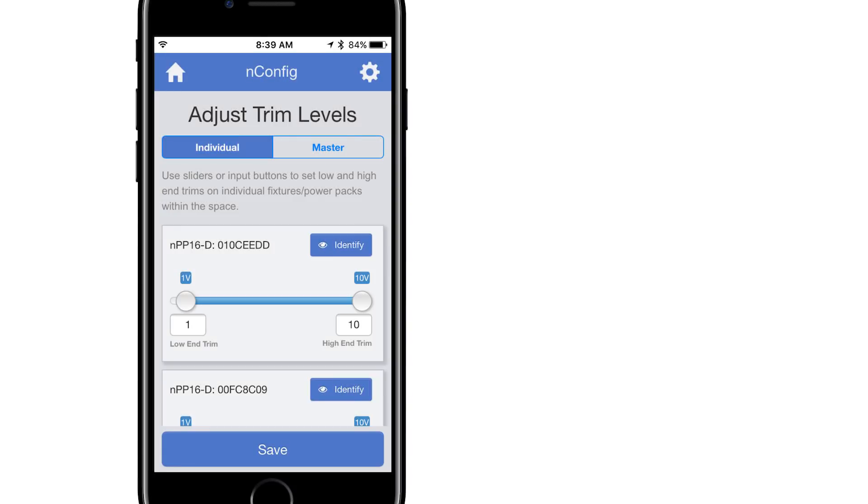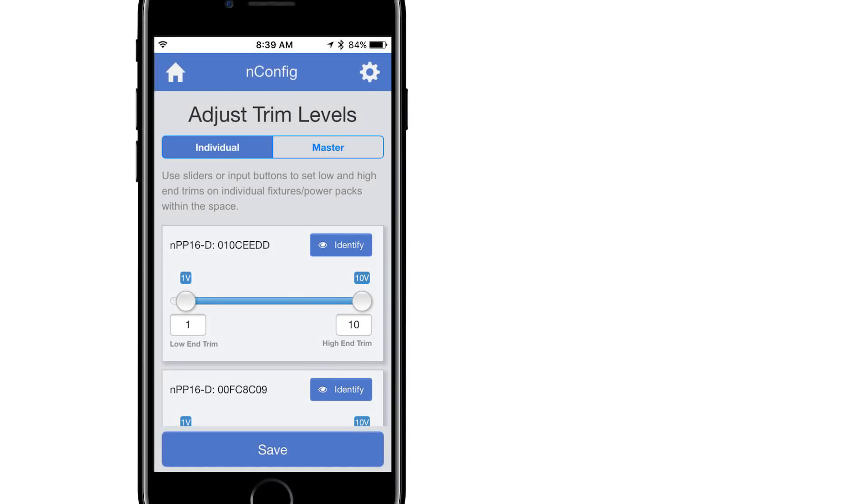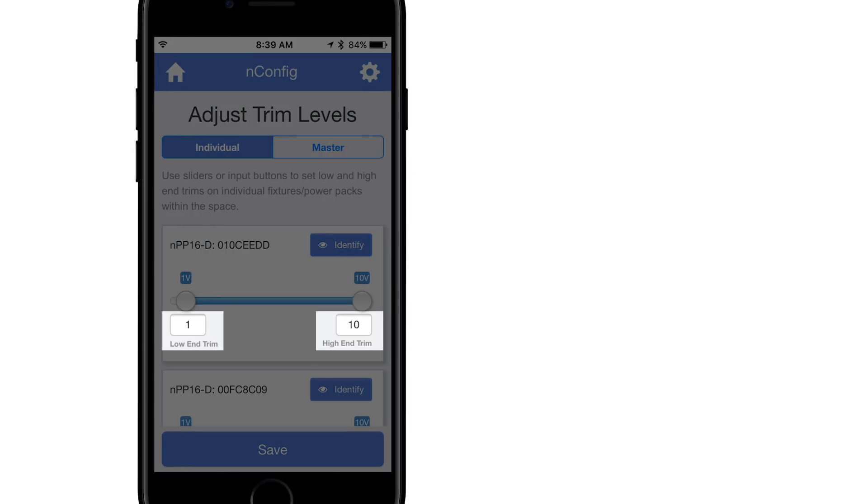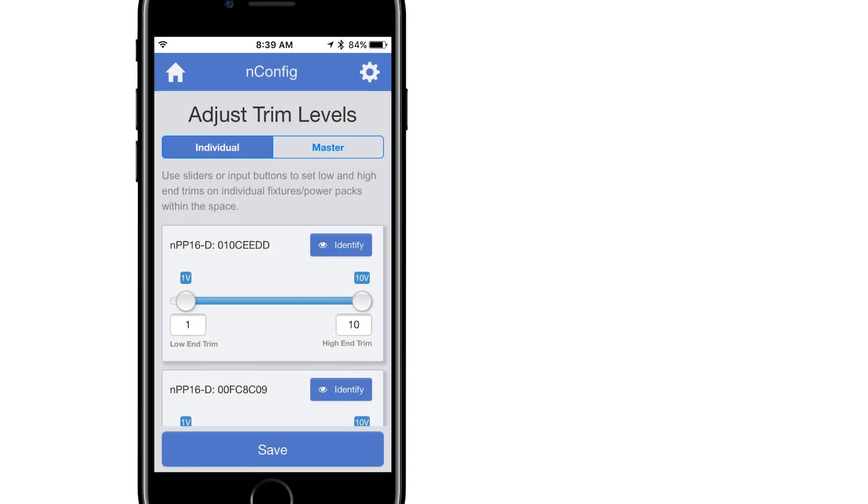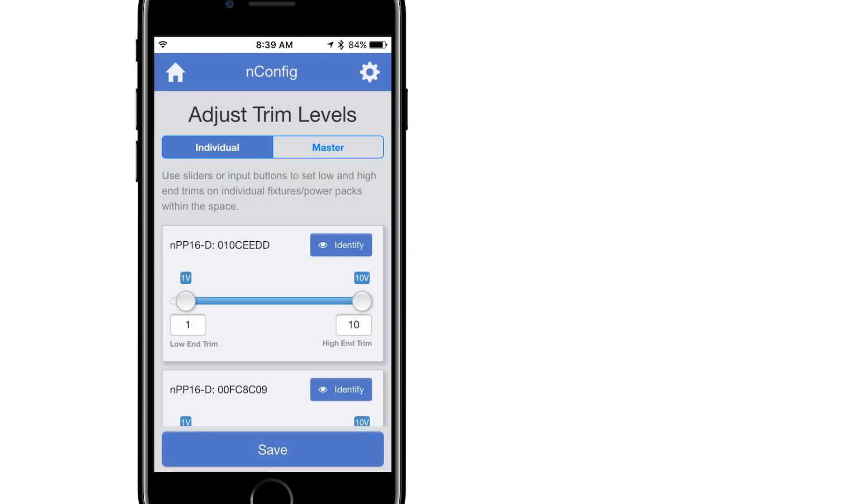Selecting Individual pulls the current value for each individual dimming device in the group and allows you to set each one independently. From this screen you can identify each device, then use either the sliders or digital input boxes in Keypad to enter the appropriate trim values. Once complete, select Save. The lights will immediately adjust to the new trimmed level.